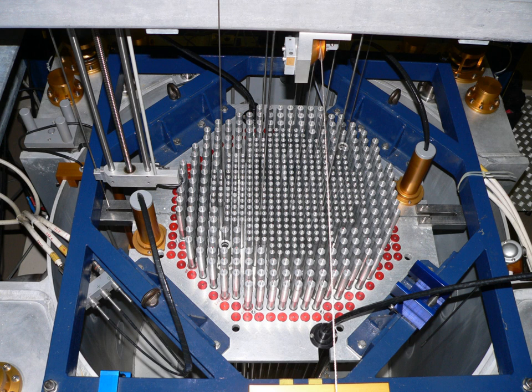Sodium cooled: Most LMFBRs are of this type. The sodium is relatively easy to obtain and work with, and it also manages to actually prevent corrosion on the various reactor parts immersed in it. However, sodium explodes violently when exposed to water, so care must be taken, but such explosions would not be vastly more violent than a leak of superheated fluid from a SCWR or PWR.